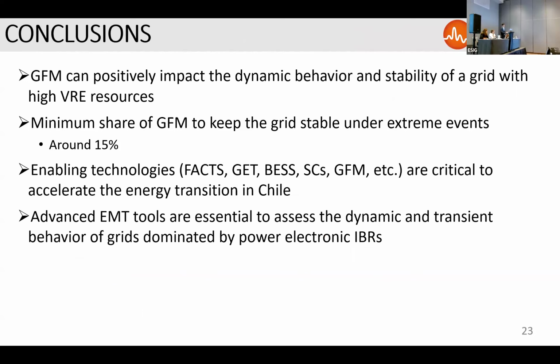All right, so this is basically the overview of the paper that we did. Some conclusions. I guess this is not going to be a surprise for anyone here in this session that yes, grid forming converters can positively impact the dynamic behavior. So it's all very good. We all know that. They also identified, based on this study, that the share of the grid forming converters that allows to keep the system stable is around 15%. Then we have seen, depending on the capacity of the GFM converters, the recovery process can be slower. It can be more difficult to recover.